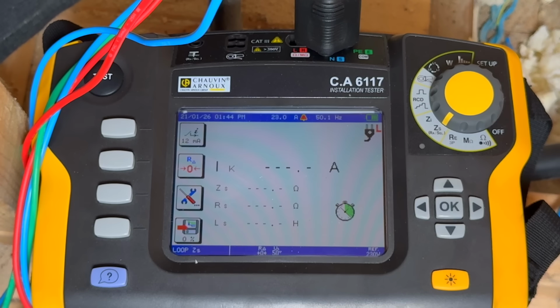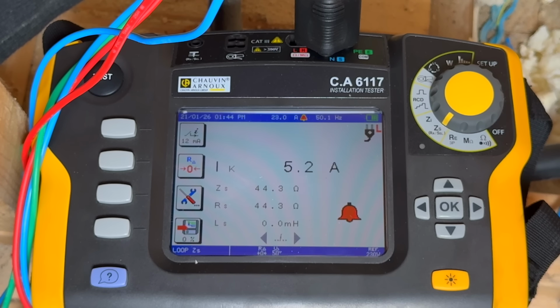So that was earth electrode resistance testing, so now it's time to look at earth fault loop impedance testing. An earth fault loop impedance test confirms that the fault path is effective enough for the protective device to operate within the required time, and it's important that we carry out both tests.